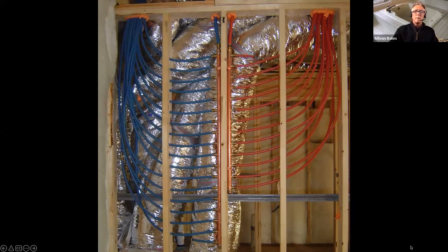This is nice in a couple of ways. Red is hot, blue is cold. On the hot side we have the manifold here, this copper manifold, and the individual home runs coming out. Notice they make these nice big sweeping turns, which is good. It's like duct systems, you don't want sharp turns that drop the pressure a lot. A sweeping turn is good.